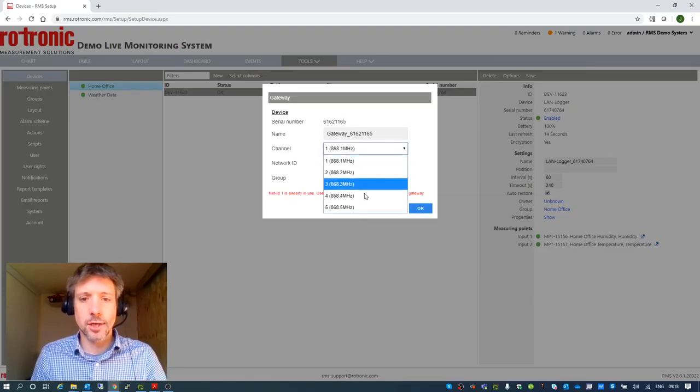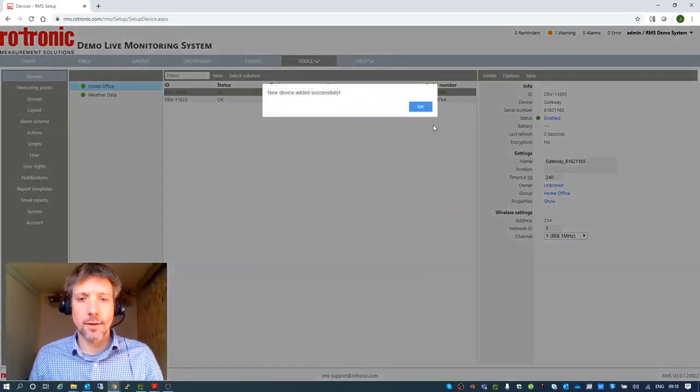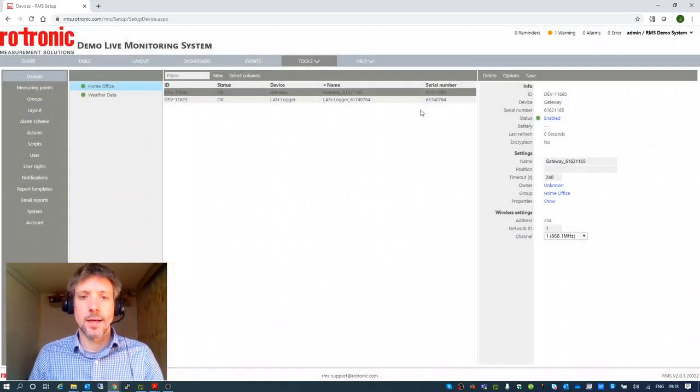I can choose various channels here. We have 6 channels in the 868 range. You can also use different network IDs to separate wireless gateways, wireless systems from other wireless systems, so we can have a lot of devices in the same area. Okay, click OK for that. That's the new device added, and that's my gateway. Nice and easy. Now I need to add my wireless logger.